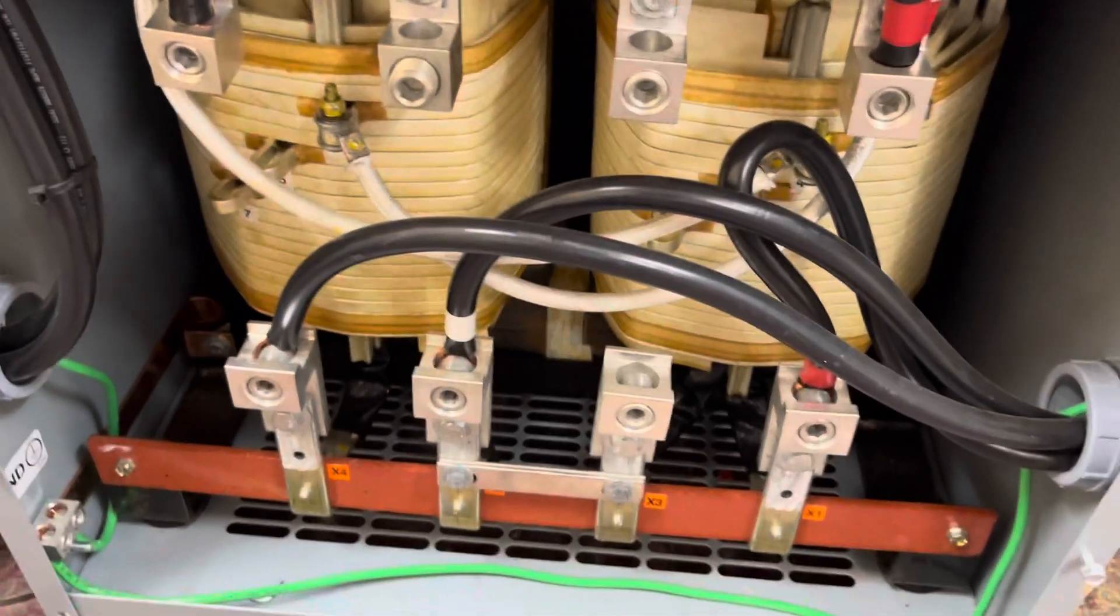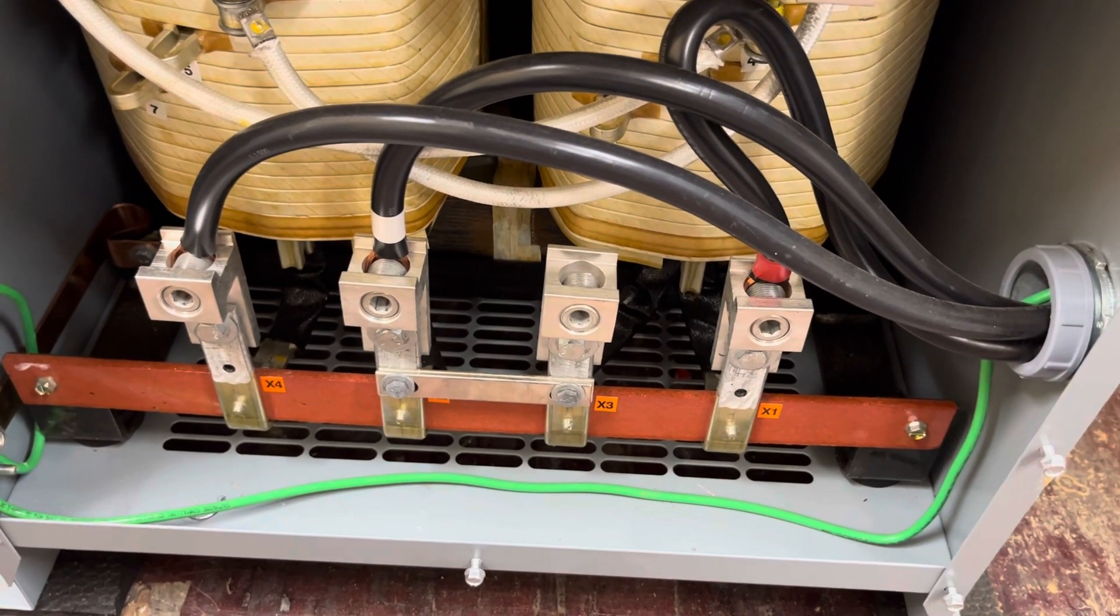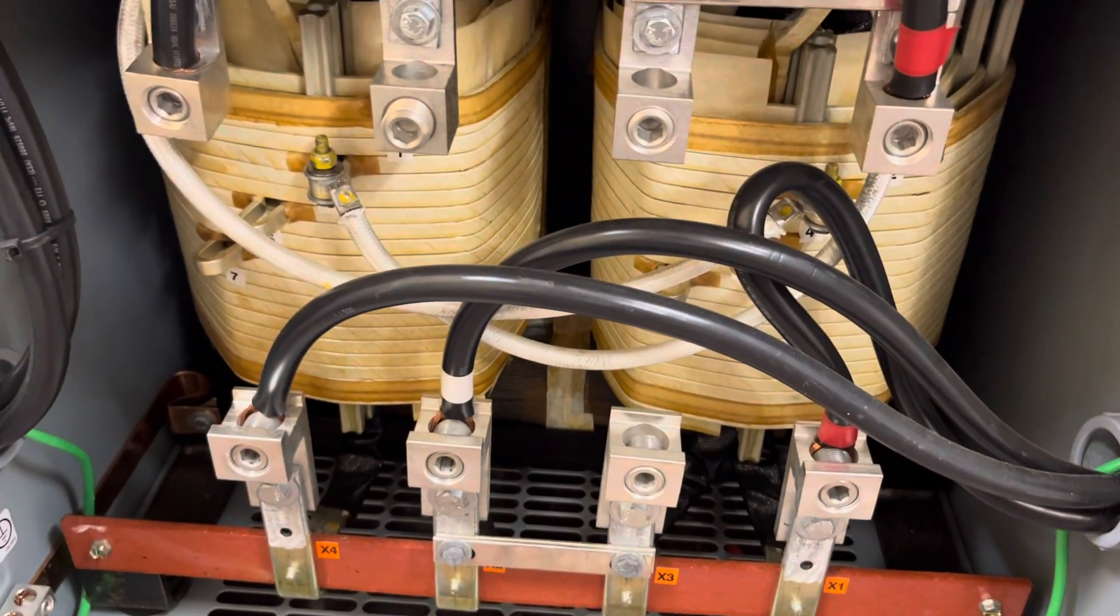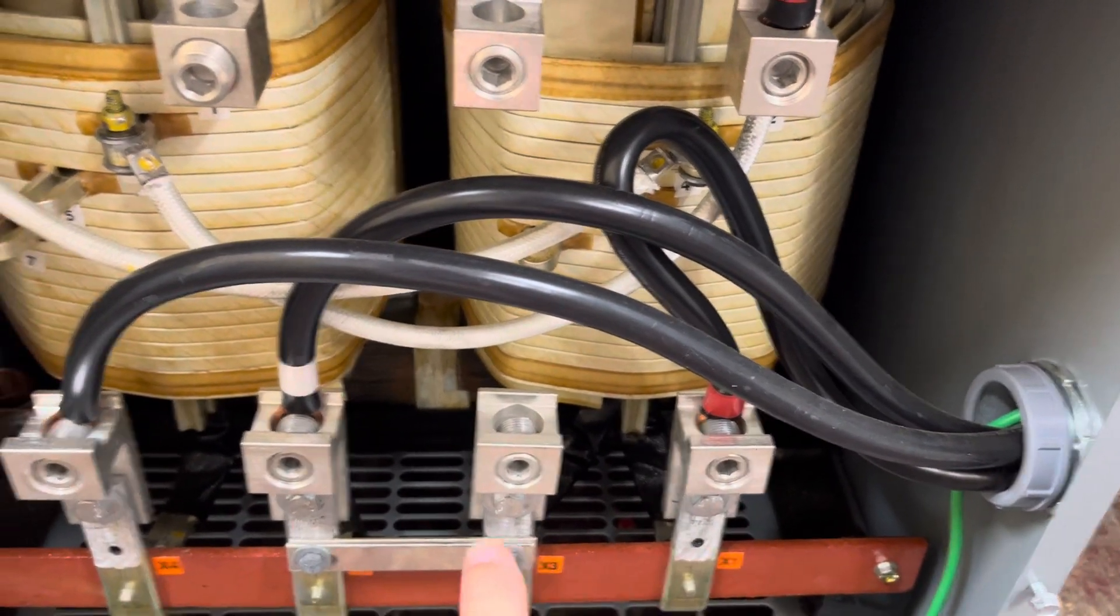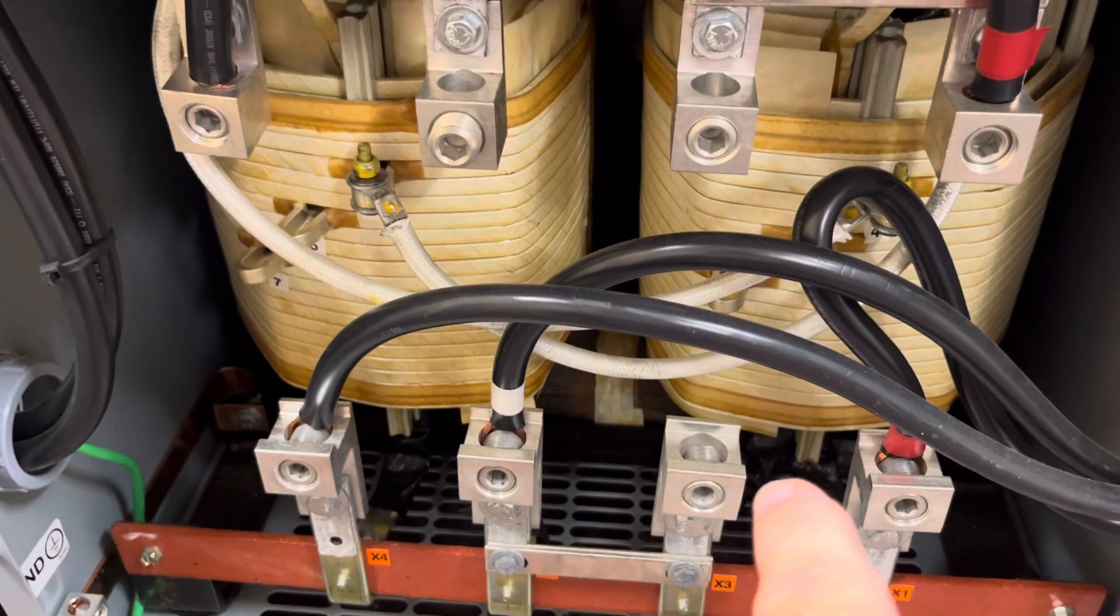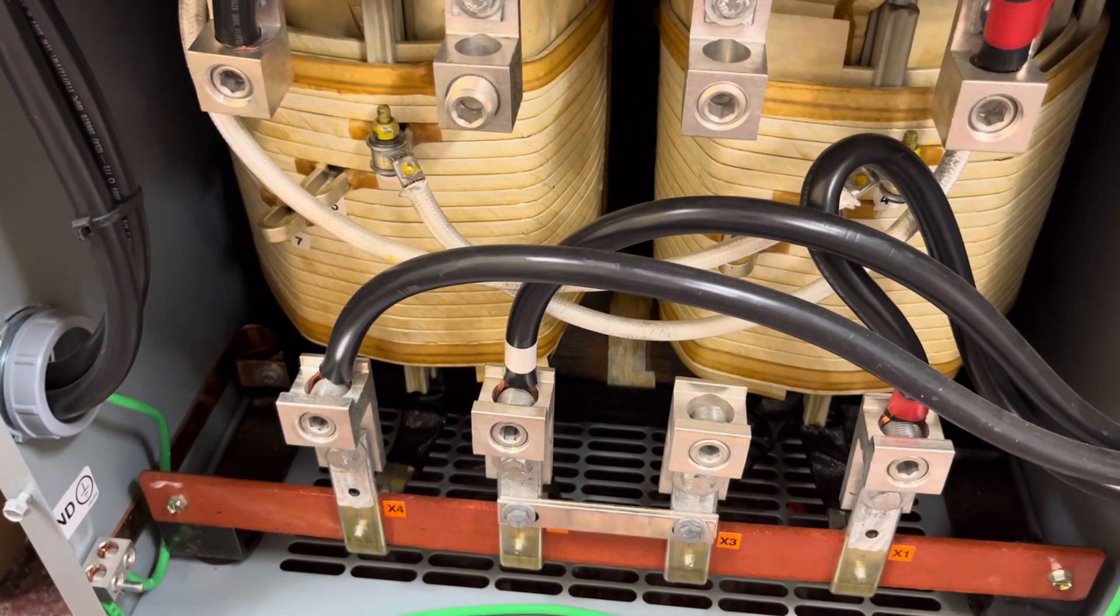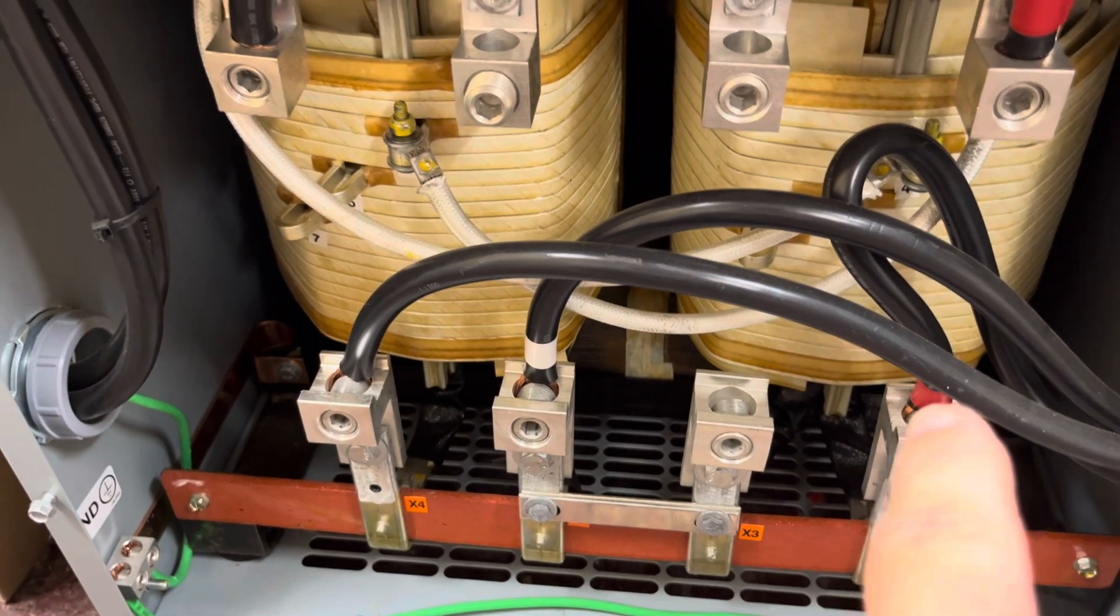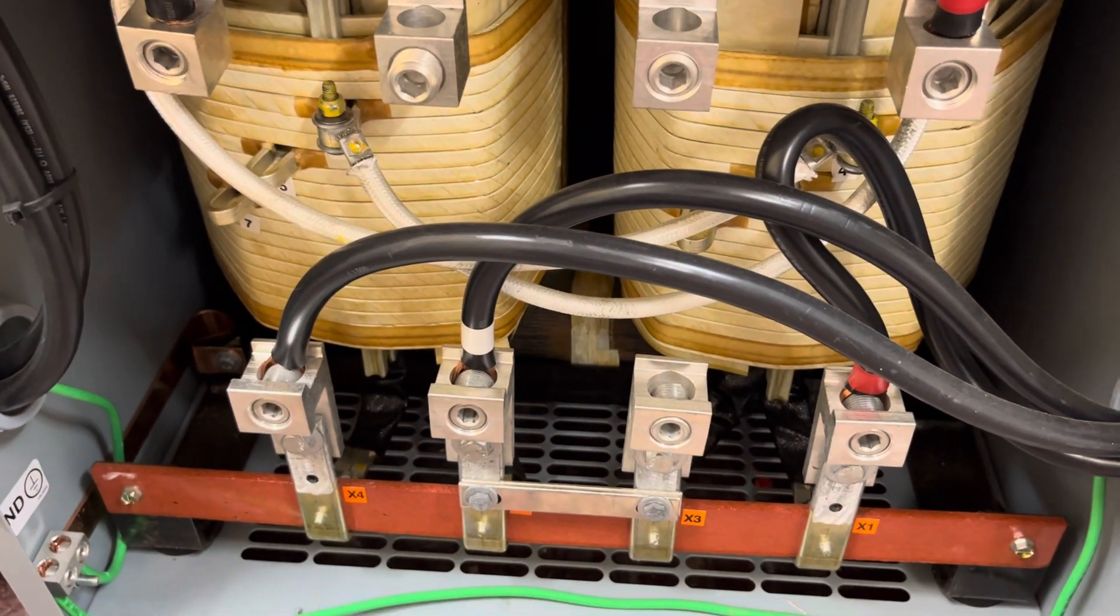Now the auto transformer has no isolation between L1 and L2 because you only have one set of windings. So when you're running in inverter mode, you have L1 coming in, L2 coming in, and then you have your neutral going out. Well, you have to have a reference for that neutral to ground for your protective circuits to work, your ground fault protection to work, and for your personal safety. So you have to ground that neutral at the first panel on the load side of the auto transformer.